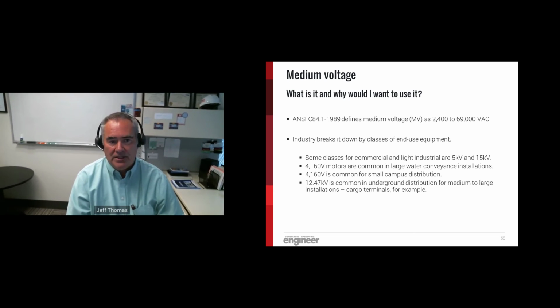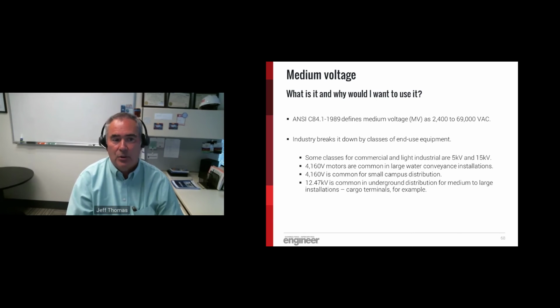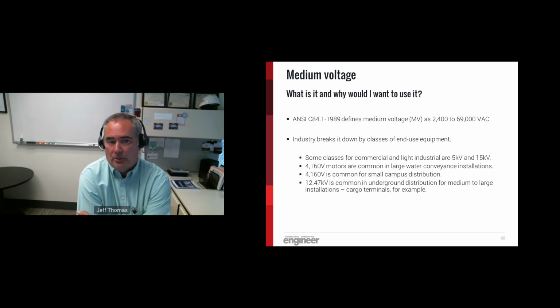And then industry breaks it down by classes of the end use equipment. 4160 volt motors are very common, and that's what's considered 5 kV stuff. 12,470 is a common underground distribution for medium to large installations, cargo terminals, for example, that have great distances to cover and large loads. That's in the 15 kV class. You'll also find 13,000 volt distribution.